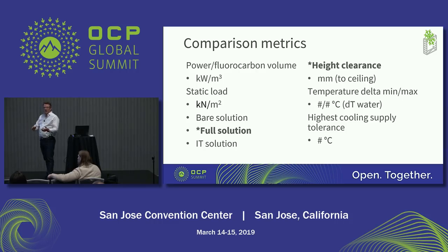Let's say you've got a dry cooler strategy. Increasing the temperature on the water circuit, increasing the delta on the water circuit, will greatly enhance the efficiency of the dry cooler. Simply because you're working with lower flow rates and higher deltas, especially compared to the outside temperature which you're relying on, which makes your heat exchange a lot more effective and efficient. So capitalizing on higher deltas will give you a lot of benefit towards your total facility efficiency.